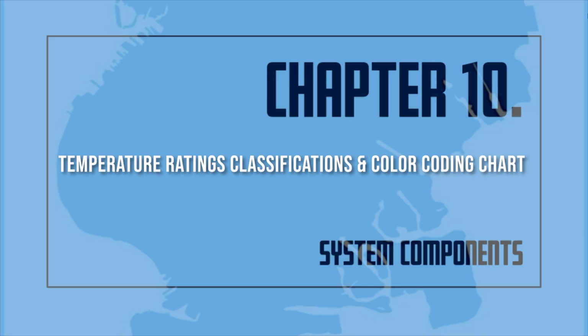cover. Sprinklers shall have their frame arms, deflector, coating material, or liquid bulb colored according to the following table. Temperature ratings classifications and color coding. For a maximum ceiling temperature of 100 degrees Fahrenheit, with a temperature rating of 135 to 170 degrees Fahrenheit, and a temperature classification of ordinary, with a frame color code of uncolored or black, the glass bulb colors would be orange or red.